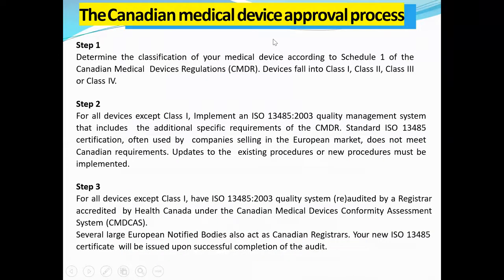So how do we get marketing approval in Canada? Step one is to determine the classification of your medical device according to Schedule 1 of the Canadian Medical Device Regulations, which is called CMDR. The devices fall into class 1, class 2, class 3 and class 4. For all devices except class 1, implement an ISO 13485:2016 quality management system.